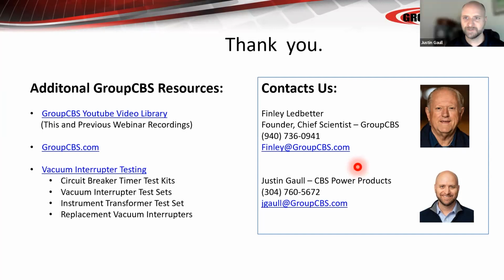Yeah, thanks, Finley. I do have a comment followed by a question. This one says, we do not have the ability or time to perform primary injection testing on most of our low voltage breakers. Can you give more insight on how often breakers should be sent out for this type of testing? Also, we do secondary injection testing at a maximum of every 5 years. That's pretty common. We're seeing more of that. You know, primary injection is slow. Now, is it slow compared to a failure?